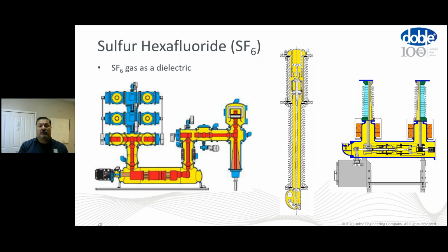But yet a lot of SF6, right? There'd be a high volume of it throughout its chambers. On a live circuit breaker, for example, the one in the middle, not only would it be found in the interrupting chamber up at the top, but also in the supporting column and even in some of the transmission components, depending on its design. On a dead tank, like the one on the far right, it's throughout its whole tank, throughout the volume of the bushings as well, and in this case, you see that the CTs are outside the SF6 compartment. But in some cases, you'll find the CTs inside the SF6 compartment, especially when it comes to GIS or gas insulated substations.